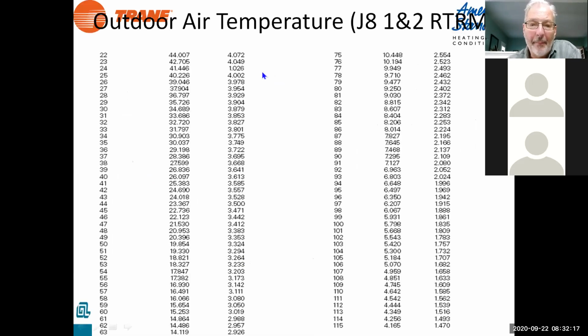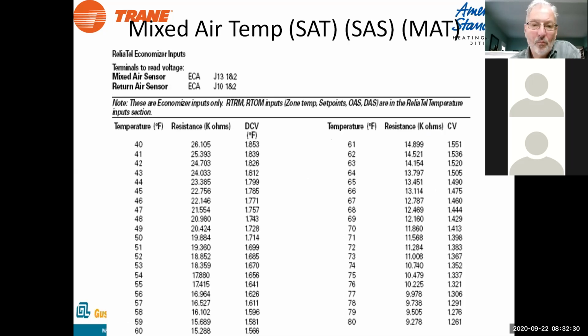We do have temperature readings for the sensors. So if it's 86 outside, you're going to see 8,000 ohms or 2.24 volts. Mixed air temperature, same thing. There are different values for the mixed air sensor. These are typically 10K at 77 degrees. So if you know it's 77 degrees, it's going to be a 10K resistor.